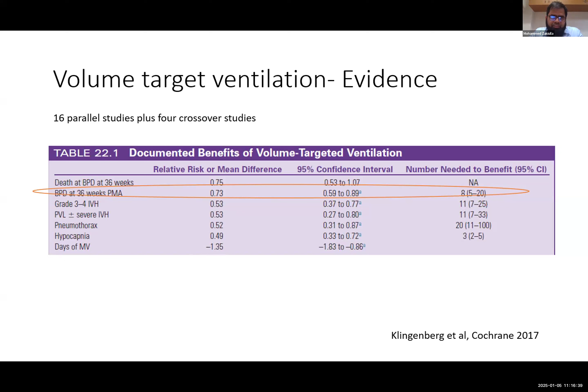But here in HFO, high frequency, what is HFO? What are you giving here in high frequency ventilation? The basic concept is two things. One is you are giving very small tidal volume, less than the dead space. We have seen, based on the systematic review, that if you target the tidal volume to 4 to 5 ml per kg, then babies will have significant benefit. But in high frequency, we are using a very small tidal volume, also less than the dead space, around 1.5 to 2 ml per kg.